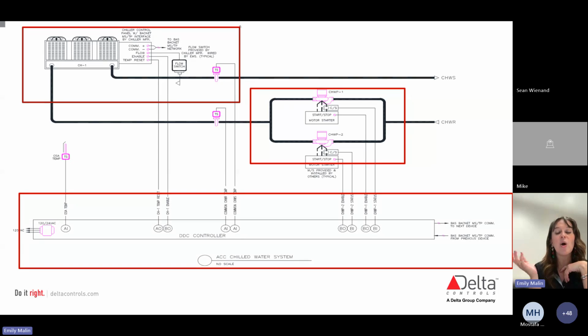Again, you can see whether or not those are going to be inputs, outputs, whether or not they're going to be analog or digital. So as we look on here too, you'll see there's a couple of other ancillary items. We're seeing there that there is going to be an outside air temperature. So again, that's monitoring the outside air temperature. I think on there we see a couple of different temperature sensors. One is going to be on that chilled water supply, and one is going to be on the chilled water return. These are going to be our analog inputs, right? Because we need to be thinking about there's a range of values. So we're looking for more than just that binary on-off. We're looking for what that range of values actually is.